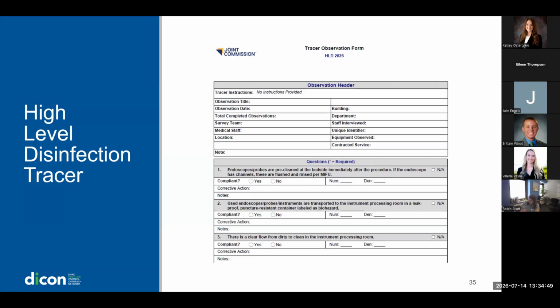The tracer tool is divided into sections such as pre-cleaning, PPE usage, the reprocessing environment, instrument transport, leak testing if it's applicable, manual cleaning, again, the use of flushing aids and brushes if applicable, high-level disinfection, either manually or with an automated endoscope reprocessor, followed by rinsing, drying, and storage. And lastly, the tool also asks questions to assess high-level disinfection documentation, endoscope repair, and equipment maintenance.